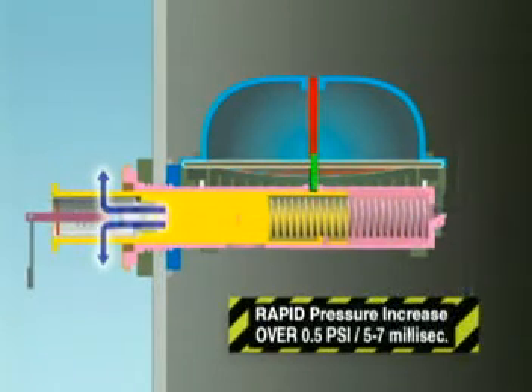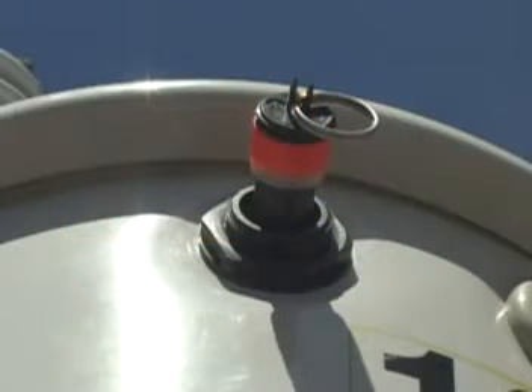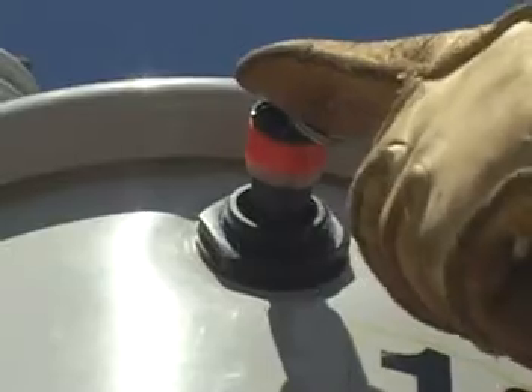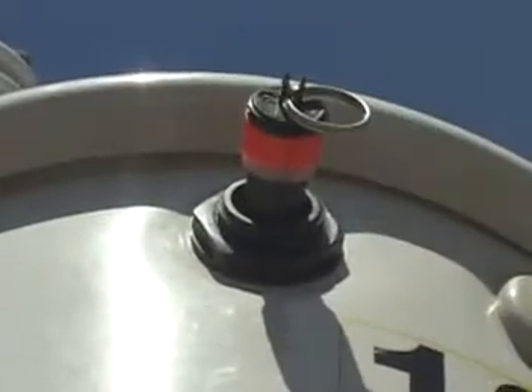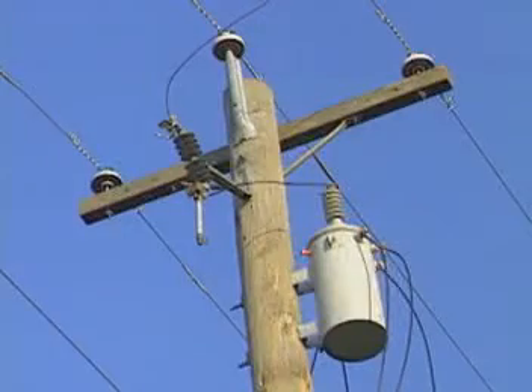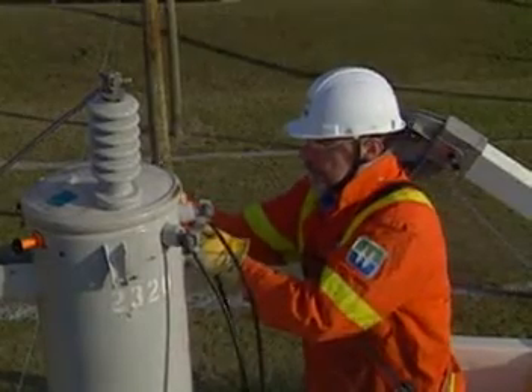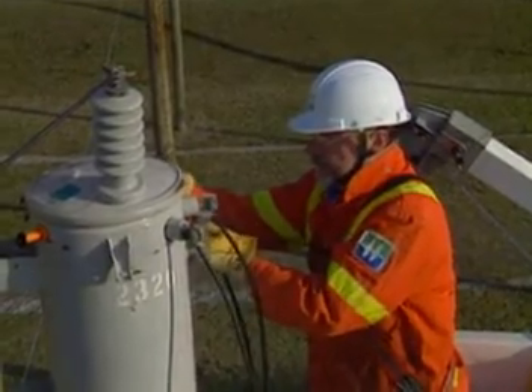Once activated, the IFD will indicate to the line worker that there is an internal fault in the transformer and that it must not be re-energized. Note that the highly visible indicator flag cannot be reset. The highly visible flag has been designed for easy identification in daylight and also in the dark with a flashlight. An IFD-equipped transformer with a highly visible flag protruding must be taken out of service and replaced.